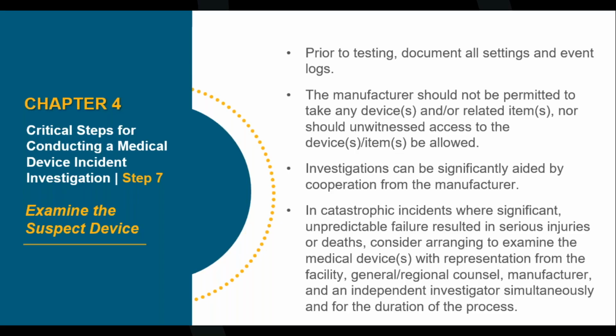Investigations can be significantly aided by the manufacturer once we do all of our testing, collect the logs, evaluate them, and do our functional checks. In catastrophic incidents where a significant unpredictable failure resulted, consider arranging to examine the medical devices with representation from the manufacturer and the facility at the same time. You may need to have general counsel or legal counsel involved as well.